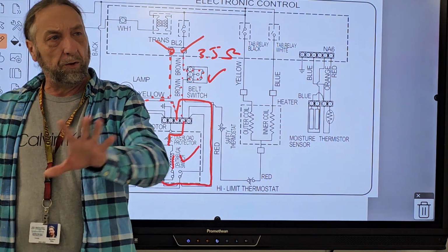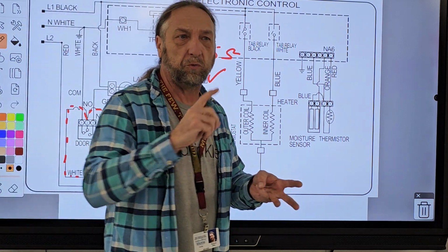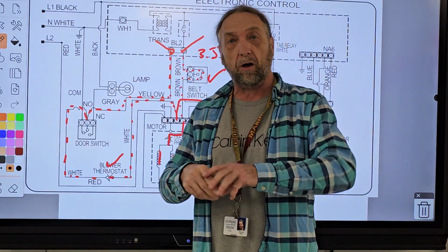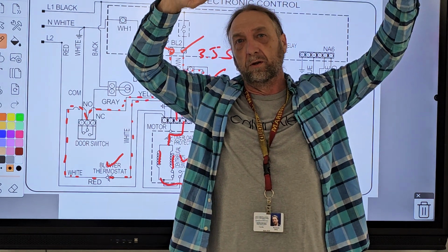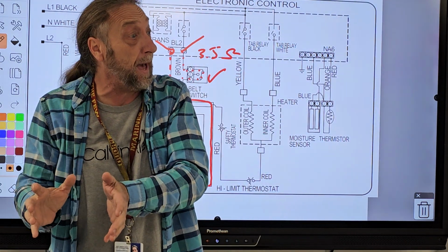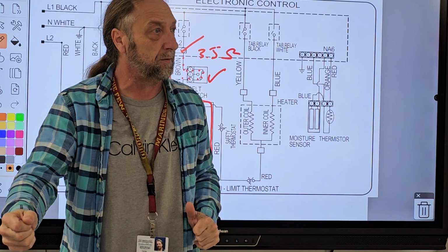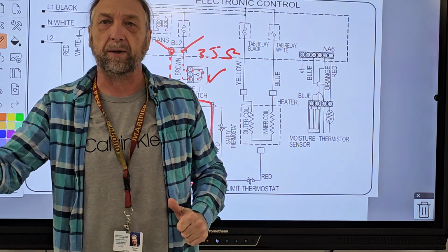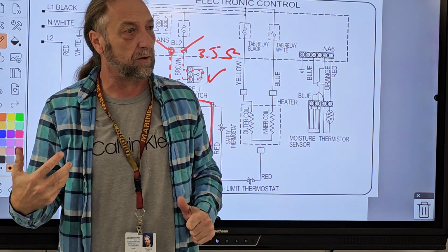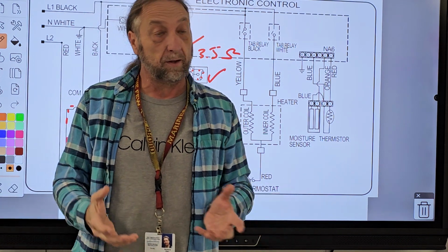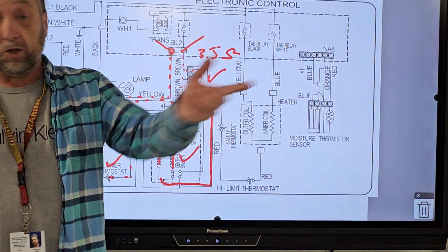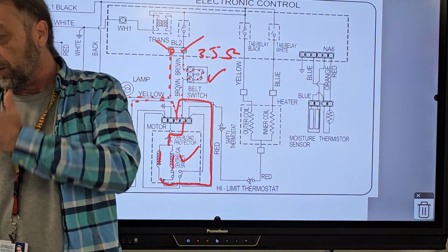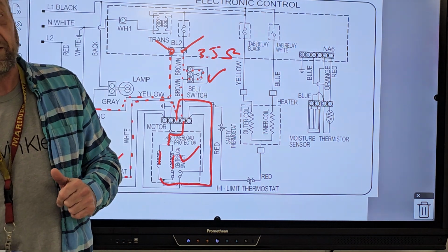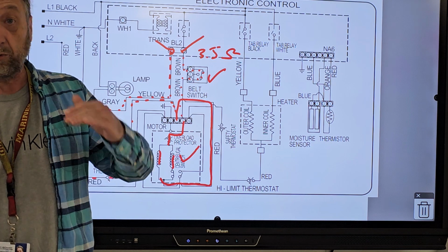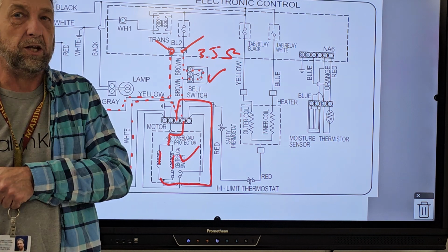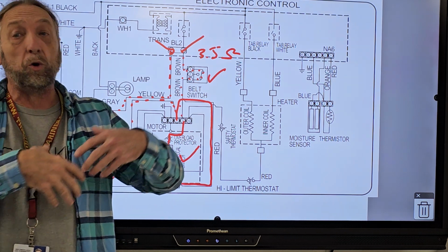Not only are all those parts good, the motor's good, the belt switch is good, the blower is good, but also all the wires going to the motor are good. Even if the motor was physically bad, when I press start, what would happen? If the motor tried to run but didn't run, what would I notice? You would hear it. You'd hear the relay on the board clicking, because if the motor doesn't run, you could possibly hear a click, that the relay was trying to send power to the motor. And you could hear if the motor's getting power, because the motor would hum.